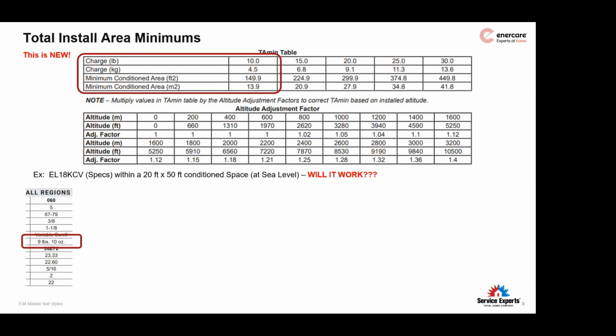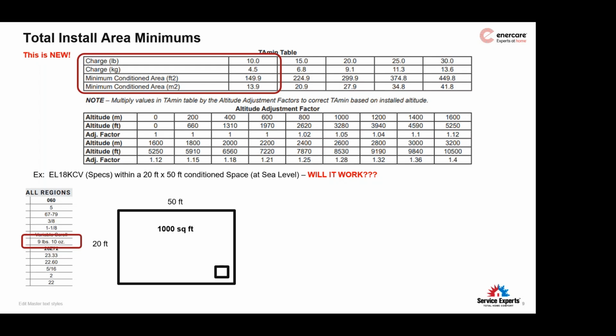Continuing with the 5-ton, let's make an assumption. We're going to put it in a 1,000 square foot building or home with a gas-fired furnace. That's what you're seeing in the corner picture there. And you're going to install a new A2L EL18KCV 5-ton. According to the TA min chart at the very top, which is right up here, is this home suitable for our new 5-ton A2L system? Do we have enough minimum conditioned area to satisfy that TA minimum table on the very top?